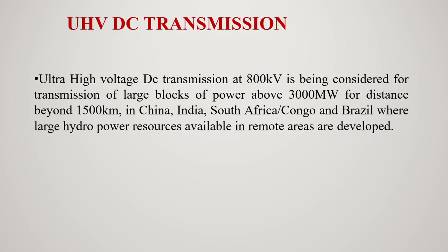A bipolar HVDC line operating at plus or minus 800 kilovolt can transmit power in the range up to 5000 or 6000 megawatt with two 12 pulse converters per pole. It is claimed that information currently available on the flashover and withstand characteristics of air gaps is adequate for design of plus or minus 800 kilovolt systems. Thyristor ratings may have to be increased by adopting 6-inch diameter wafers.